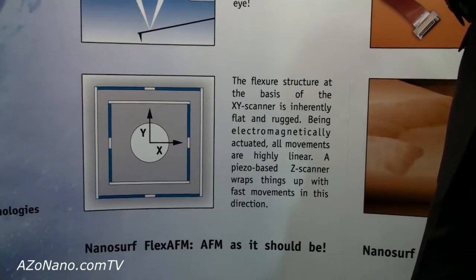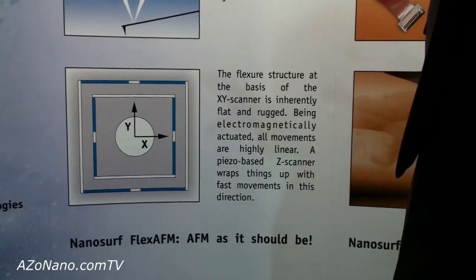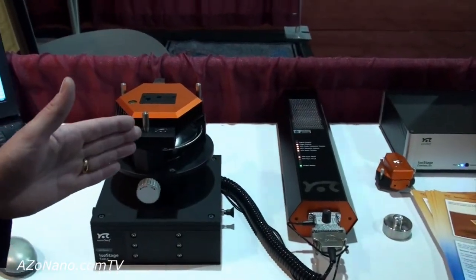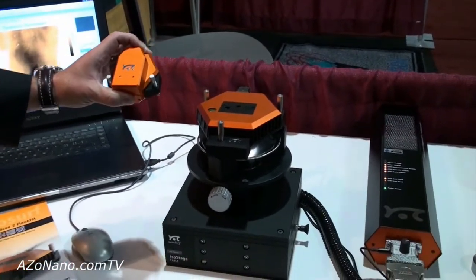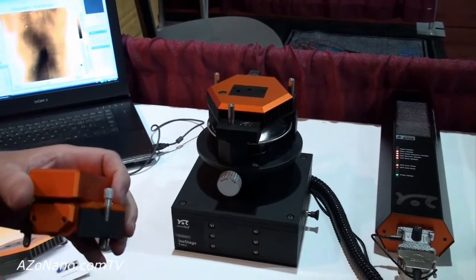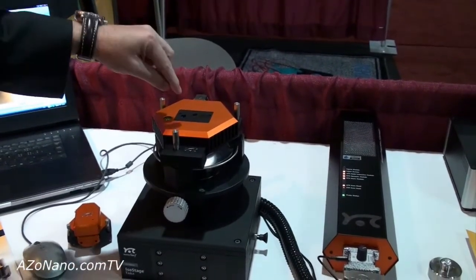The unit itself is fairly small and compact — a little bit larger than our current EasyScan 2 AFMs and STMs due to its design, but still very small and compact. You can see it live here in scale one to one. We're using the same type of controller system as our traditional EasyScan 2. One difference is that our current EasyScan 2's have the measurement in front, whereas here we're doing the measurement in the middle of the AFM, and we also have see-through optics.